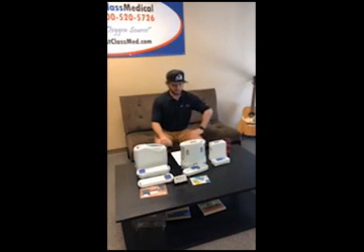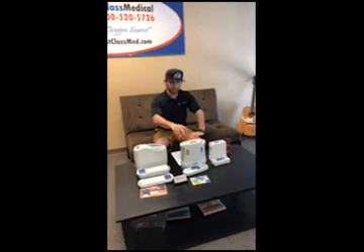So when you're looking at this unit, the big battery, little battery once again, but it's different. So this was 24 and 12 cell. The G3 is an 8 and 16 cell. So the 16 cell is going to give you 8.5 hours on a setting of 2. The 8 cell will give you 4 hours on a setting of 2. The unit itself weighs 4.8 pounds. It goes up to a setting of 5. If you've looked at the G3s when they first came out, they were setting 4. Their newer units have the high flow, which is up to a setting of 5. And once again, 8.5 hours on that 16 cell battery makes this unit one of the best units on the market in its class for battery life.